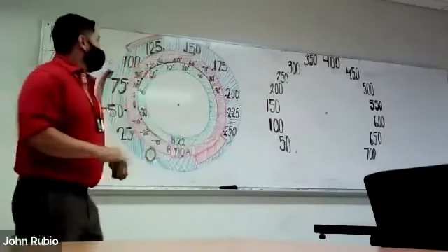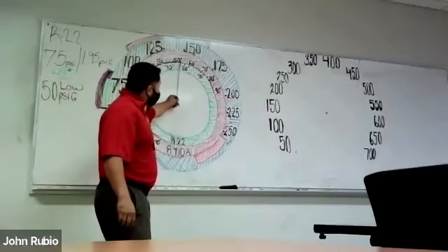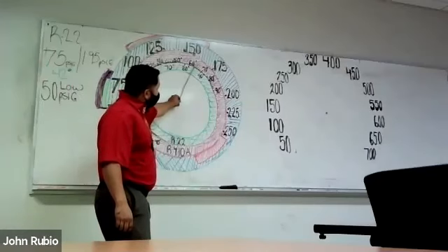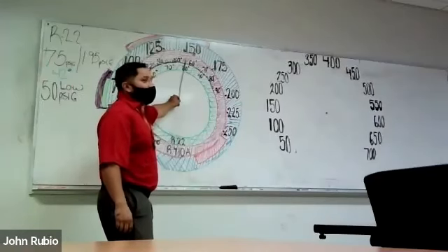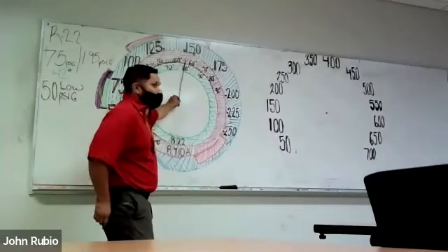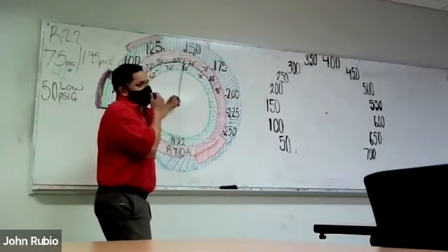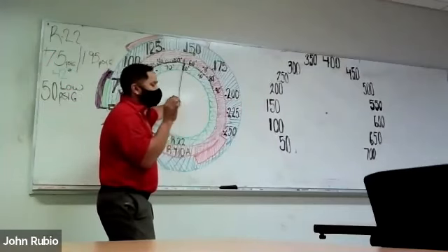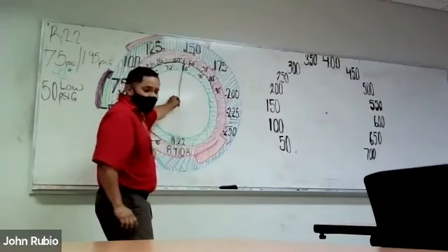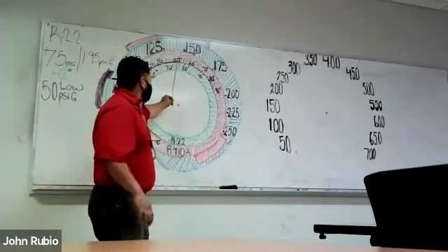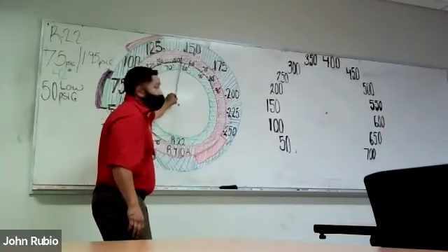If you get there and you can't go much more, you're at 149, 148, there's no more room for performance improvement, not with gauge pressure, not with superheat. Maybe with something else, maybe with duct modifications. She's got a horrible, nasty filter in there, the coil's dirty. But as far as refrigerant, I'm there.